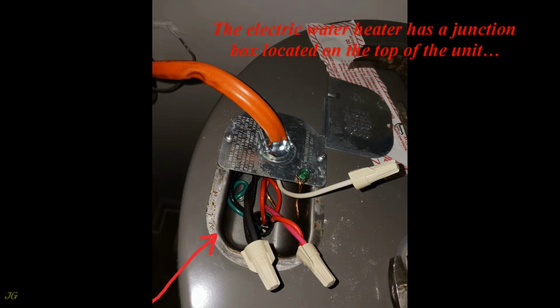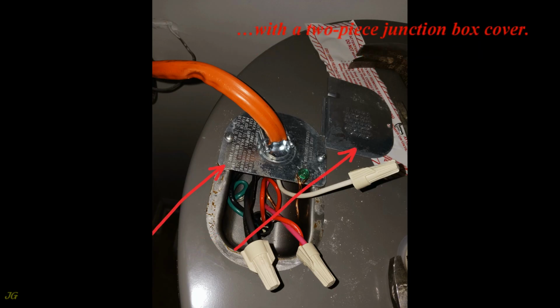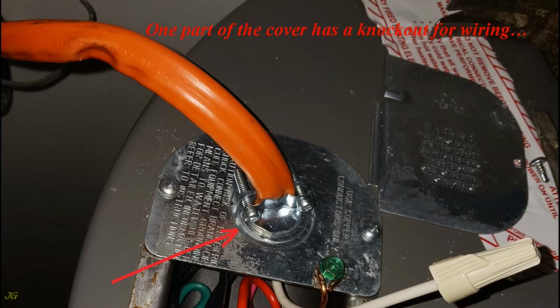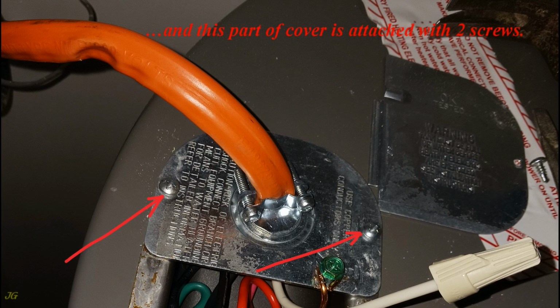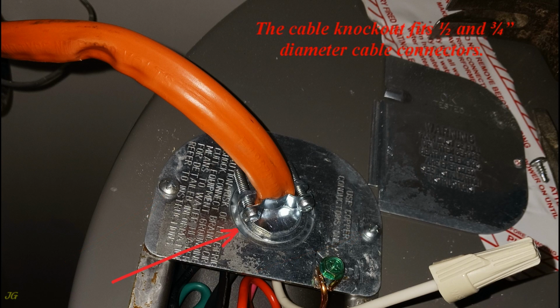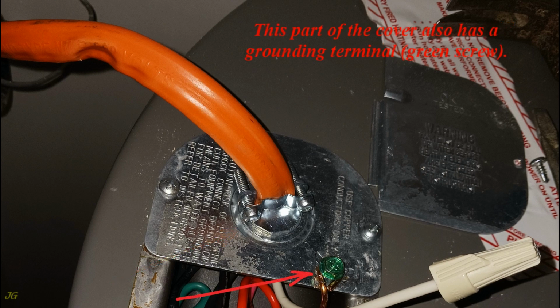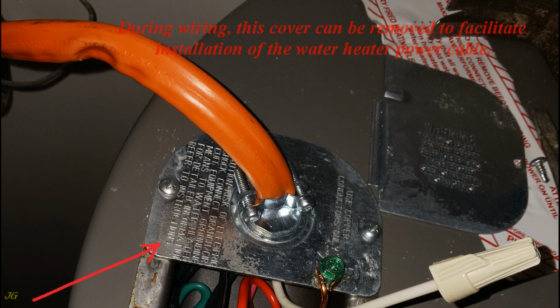The electric water heater has a junction box located on the top of the unit, with a two-piece junction box cover. One part of the cover has a knockout for wiring, and this part of the cover is attached with two screws. The cable knockout fits 1/2 and 3/4 inch diameter cable connectors. This part of the cover also has a grounding terminal, a green screw. During wiring, this cover can be removed to facilitate installation of the water heater power cable.